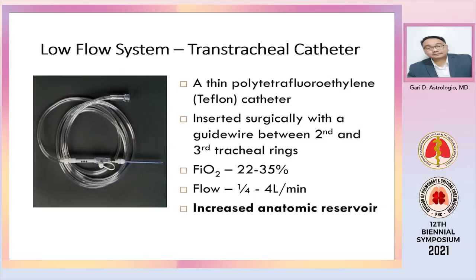With the transtracheal catheter, it makes use of a thin polytetrafluoroethylene catheter, or the Teflon, which is inserted surgically through a guide wire between the second and the third tracheal ring. Usually, you deliver a gas flow of around less than 1 to 4 liters, no, and you'll be able to reach around 22 to 35 or 40% of inspired oxygen. When you insert a transtracheal catheter, somehow you increase the anatomic reservoir.